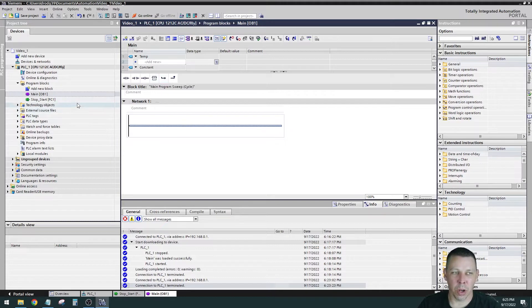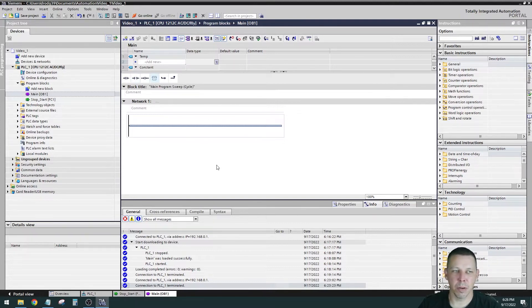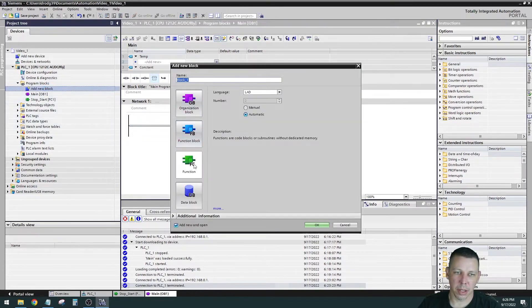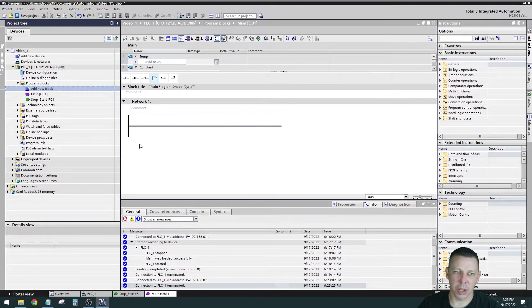People often when they first start out will go to OB1 and start dragging instructions into Network One of OB1 — that is not the standard way to do it. OB1 is the organizational block; you shouldn't have all your logic in it. It's like the block that calls subroutines. Your functions and function blocks are the ones that actually contain all the logic and processes. The organizational block just calls them in the right order.